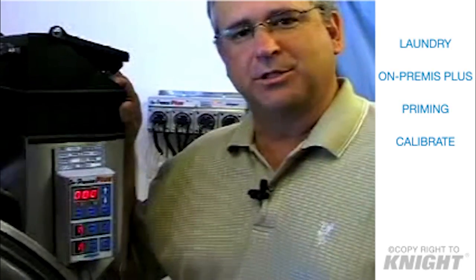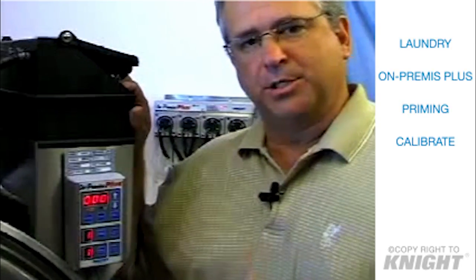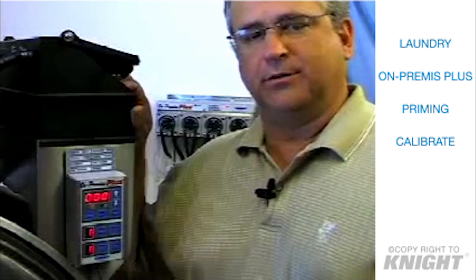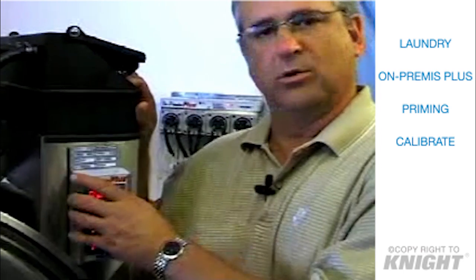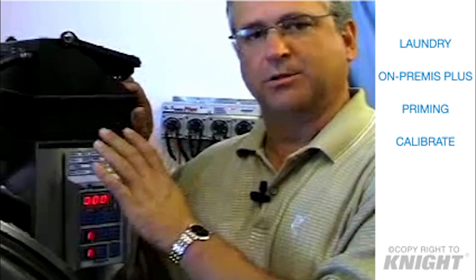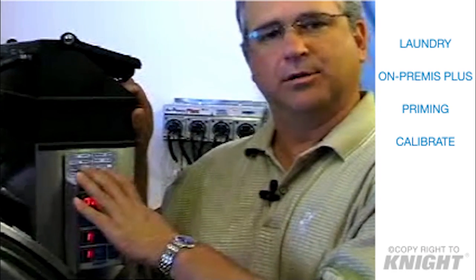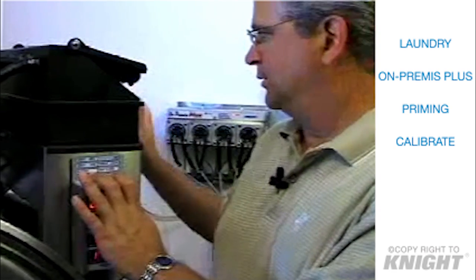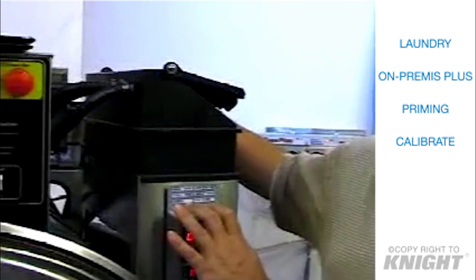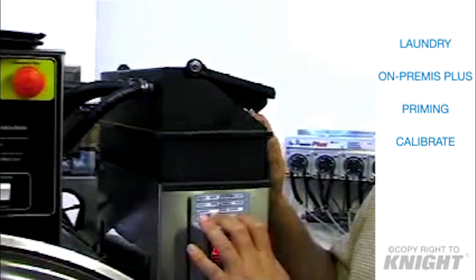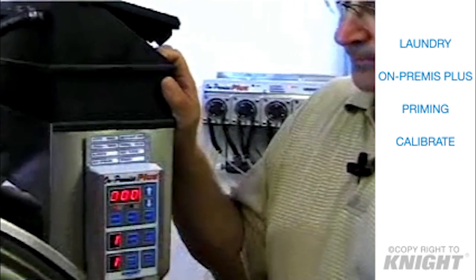Now that our dispenser is installed, it's wired to the machine for power, it's wired to the machine for our signals, our remote control is in place, our chemical supply is in place, our discharge line from the flush manifold is in the supply box. We're ready to prime the pumps. So let's go ahead and do that together.